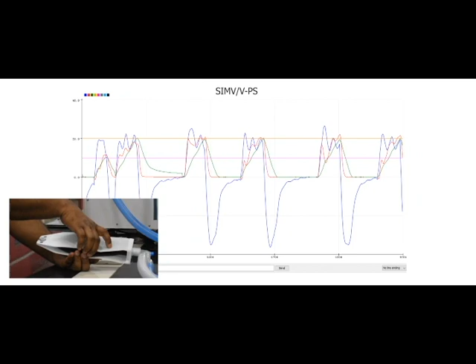And the last mode I'll be showing you now is nothing but SIMV-P. For SIMV-P, I will be setting some parameters. So let me find some good parameters over here. Let us set the pressure control at 20 centimeter of water column. Respiratory rate, let us keep at 15 BPM. Inspiration to expiration, let us have 1:2. Trigger, here also we will keep -2 centimeter of water column, and pressure support will be up to 10 centimeter of water column. Right.